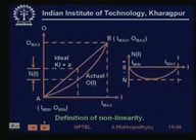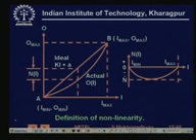So that's linearity, that it is the deviation of the calibration data from some good straight line which you have obtained either by data fitting, or in some cases it may be obtained in a different way. For example, in this case you can also obtain it, that's a simpler way, by taking the reading at the least value and the maximum value, and then simply assuming that the characteristic is going to be like this.